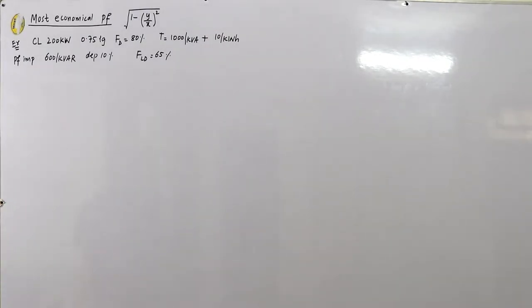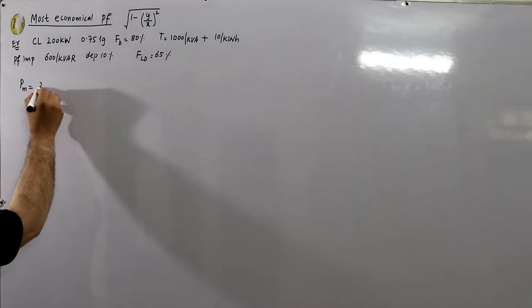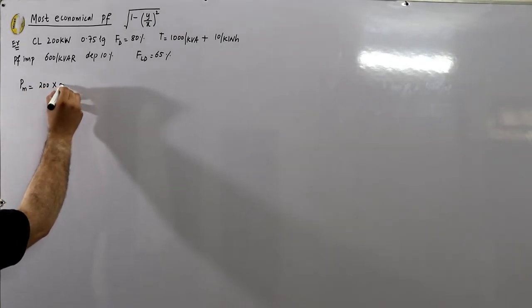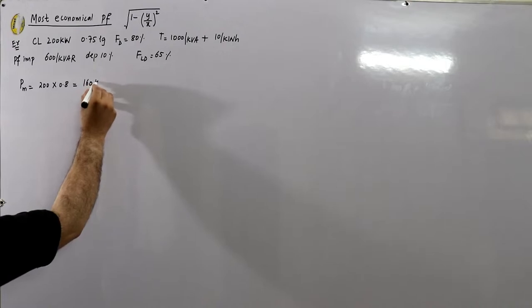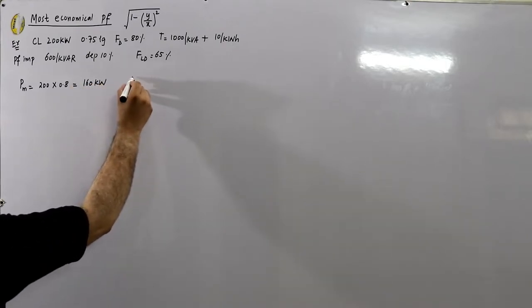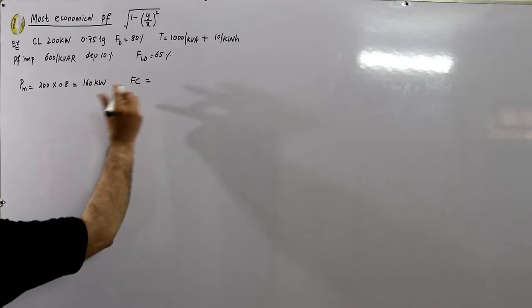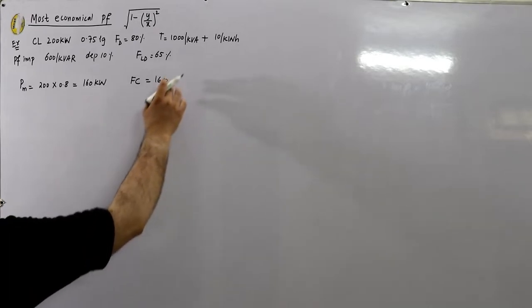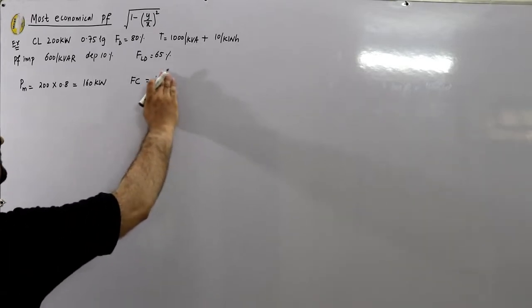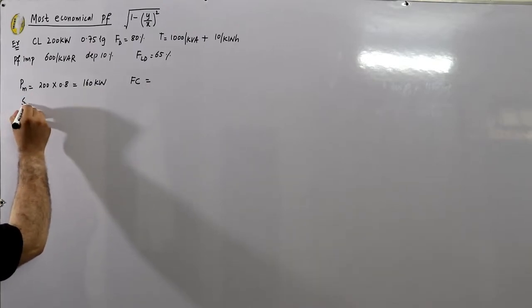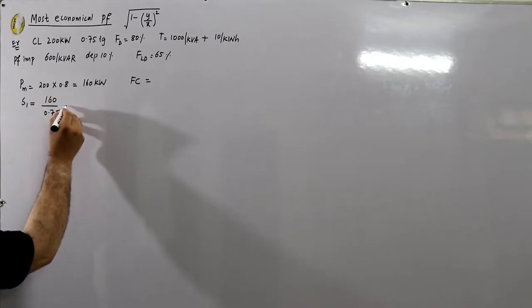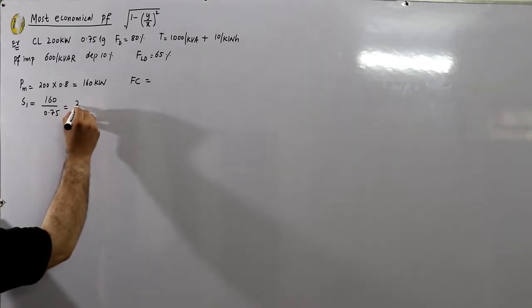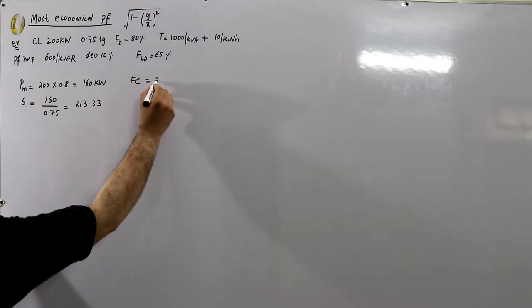For the current situation first, the maximum demand is the connected load multiplied by the demand factor, which gives 160 kilowatts. The fixed charges are based on kVA, so find the kVA: S₁ = 160 kilowatts divided by power factor 0.75, which gives 213.33 kVA.